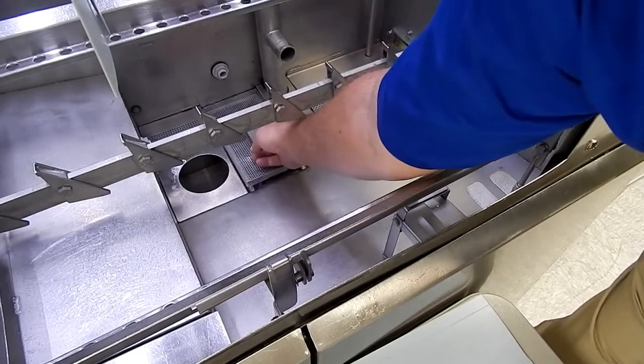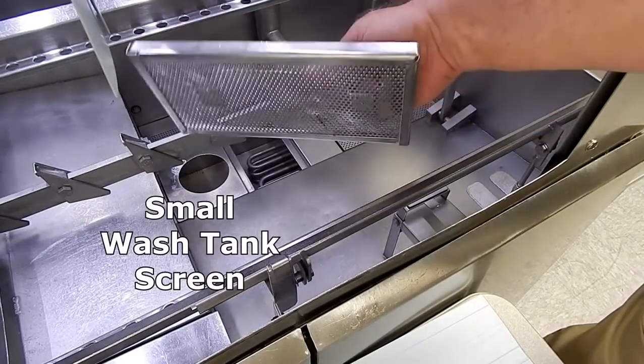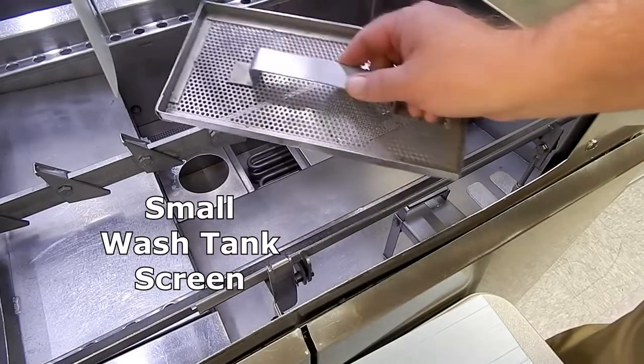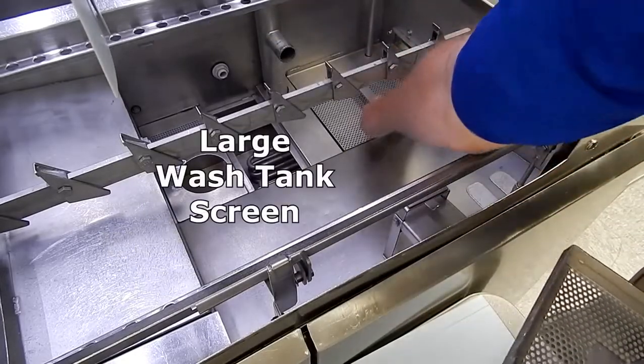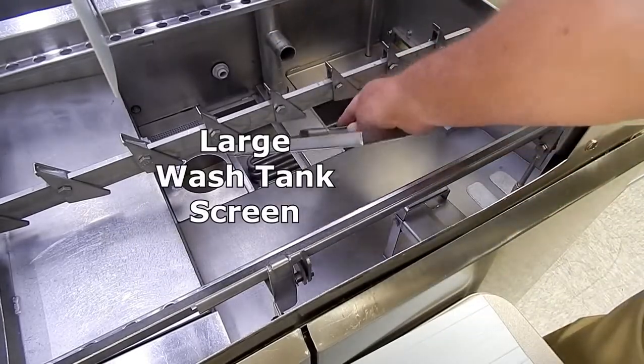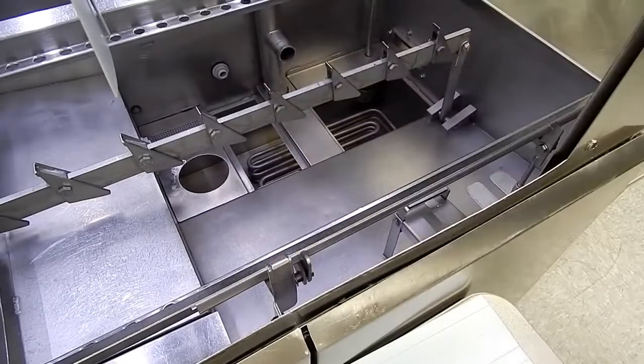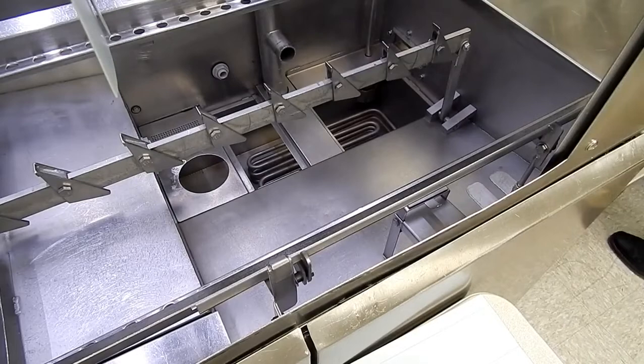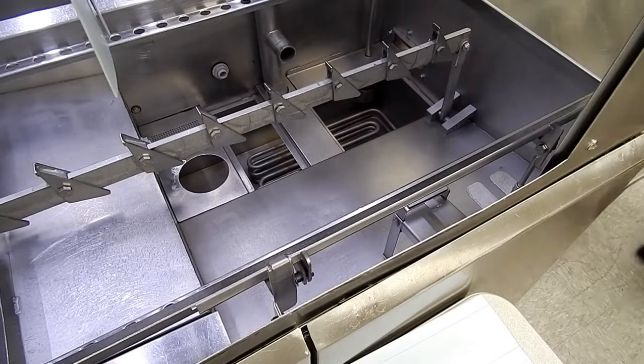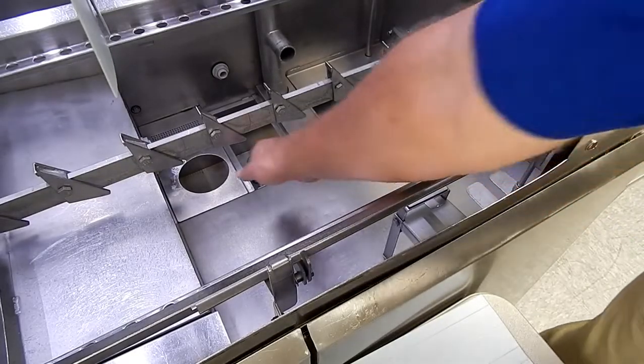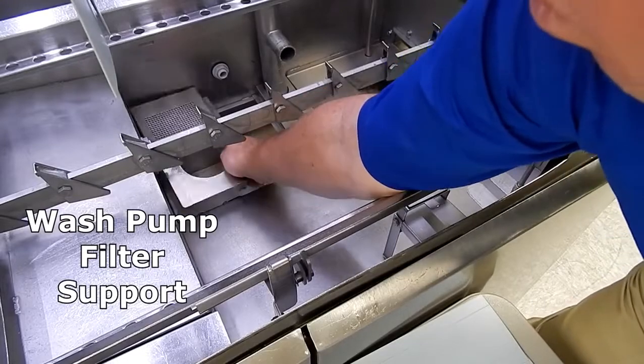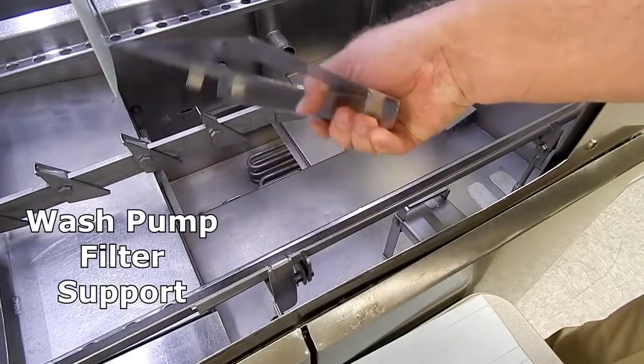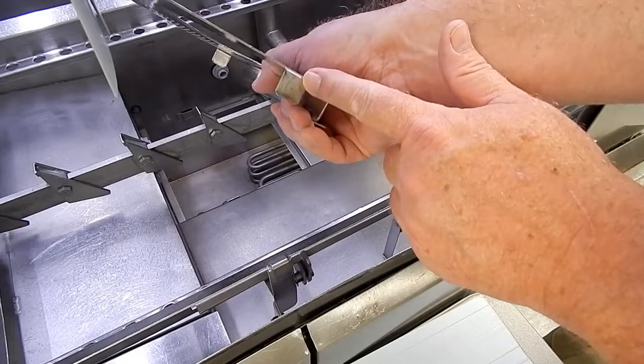Next, we remove the wash tank screens. There are two screens, a small wash tank screen and a large wash tank screen. Be sure that they're clean top and bottom. Next, we remove the wash pump filter support. This supports your wash pump filter from tilting over.